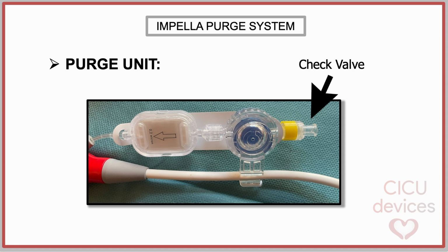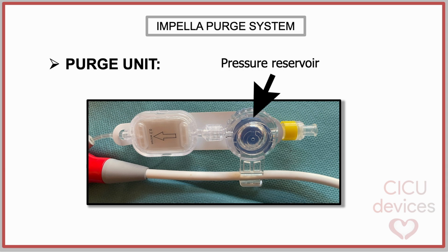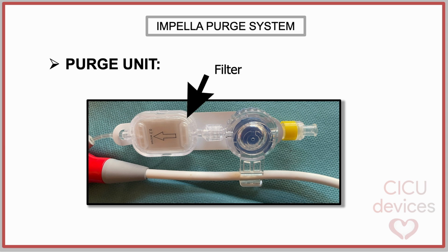At its proximal end, the purge unit incorporates an additional yellow check valve. Distal to this valve, the purge unit includes the purge pressure reservoir, an elastomeric membrane designed to temporarily maintain purge pressure for approximately 1 to 2 minutes during brief purge system disconnections. This feature helps preserve the protective pressure barrier within the motor housing and reduces the risk of blood ingress during handling or troubleshooting. A 0.2 micron filter is incorporated into the purge line to prevent particulate contamination and to maintain system sterility, which is critical for reducing infection risk and ensuring long-term device performance and durability.